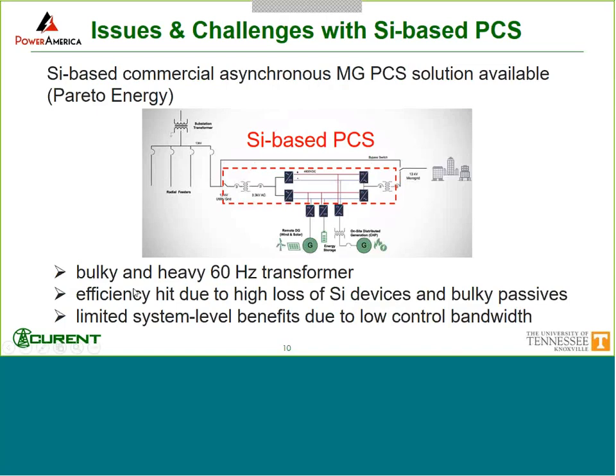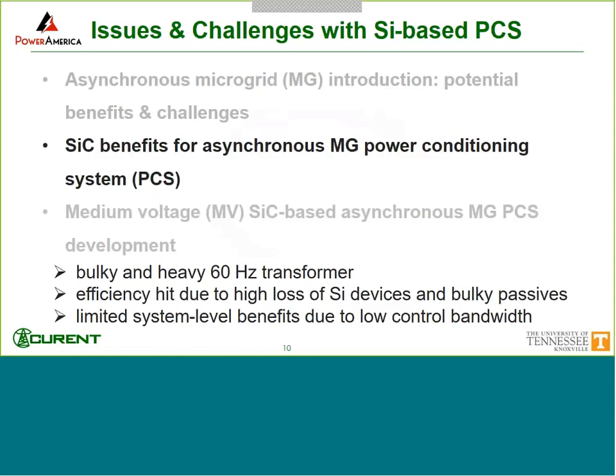And obviously, with this, we will have to have this fairly bulky and heavy 60 hertz transformer. And the overall efficiency is also something we have to deal with. Also, because of this, the IGBTs are relatively slow. At 3.3 kV, you have to use some fairly higher voltage IGBTs, and they can only switch around a kilohertz or less, so some of the system level benefits are limited, the one I mentioned, because of the limited control bandwidth.